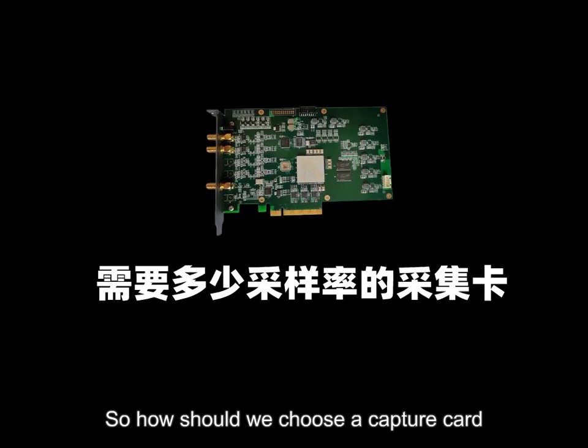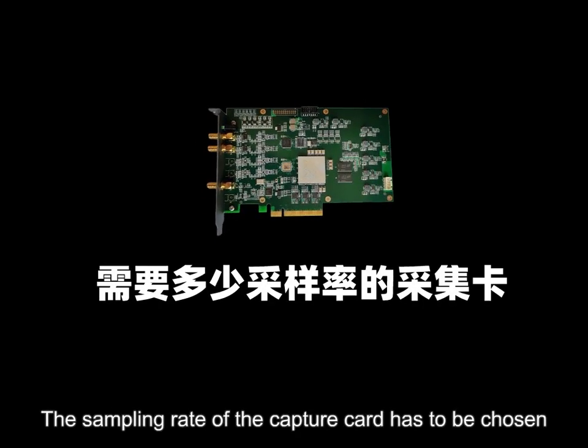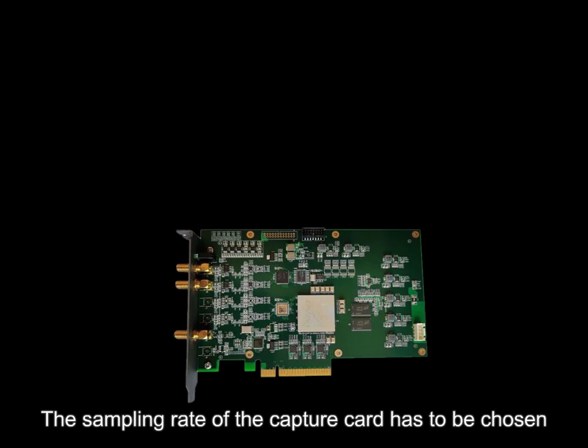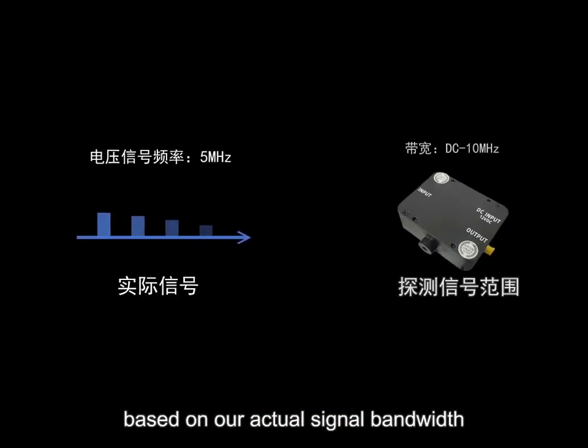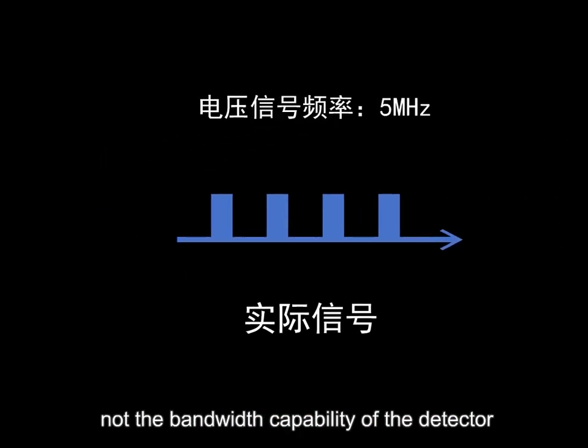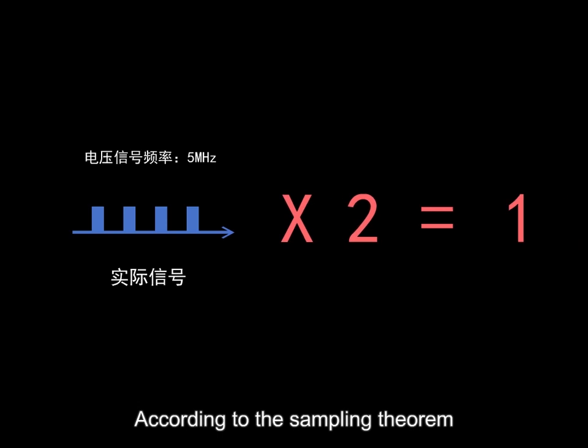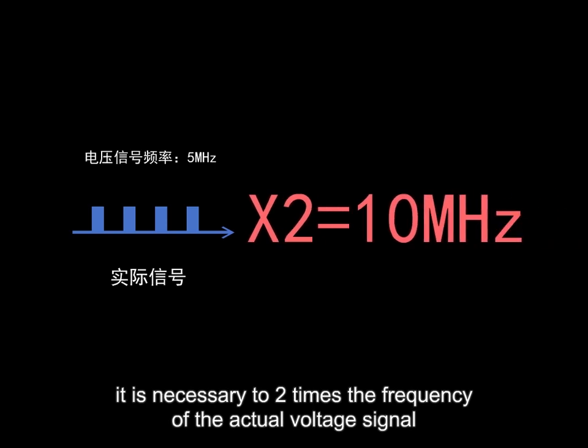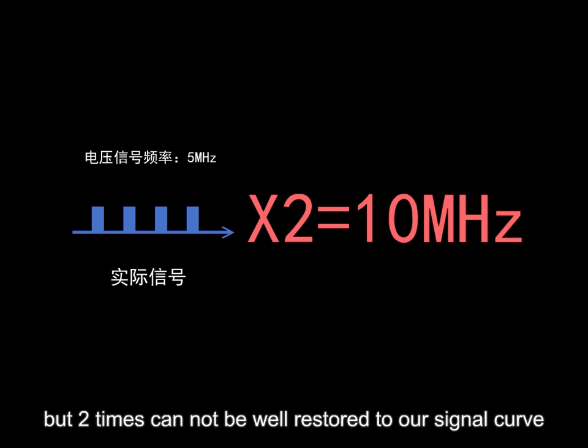When we have selected the detector, we have also evaluated the signal bandwidth for our application. So how should we choose a capture card? The sampling rate of the capture card has to be chosen based on our actual signal bandwidth, not the bandwidth capability of the detector. According to the sampling theorem, it is necessary to sample at 2 times the frequency of the actual voltage signal, but 2 times cannot restore our signal curve well.